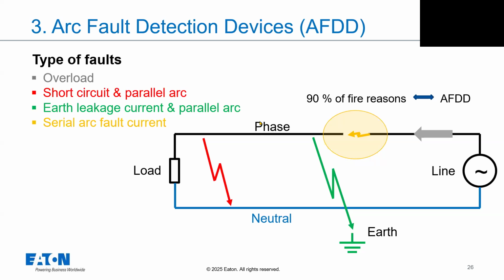Then in this case, we understand well that this green scenario will be well protected by the RCD. This red scenario will be protected by a fuse or circuit breaker. But what about this yellow case? This is a serial arc. It means, for example, a terminal is not well connected, or a conductor is a little bit cut. Then a serial arc can be created, which is a danger for insulation and so on, creation of fire. But we know from the electrical point of view, no MCB, no MCCB, no fuse, no RCD will detect this. Then only an AFDD can be used. And this is the main reason why we speak about AFDD.